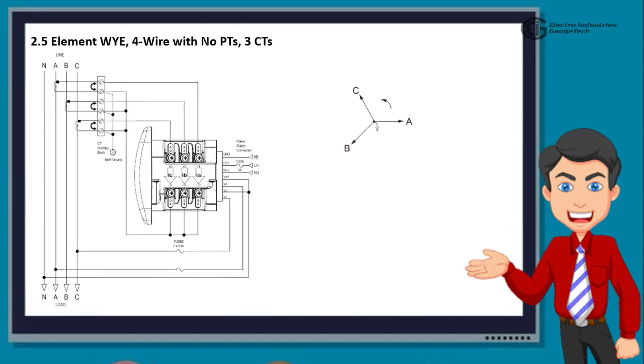Now, the next diagram shows the 2.5 element Y, 4 wire with no PTs, 3 CTs. This is a 3 phase, 4 wire system Y with direct voltage, and 2.5 element. When using this wiring, select 2.5 EL Y from the Shark Meter's front panel display.